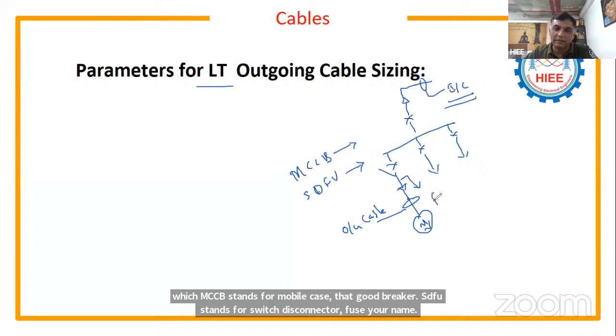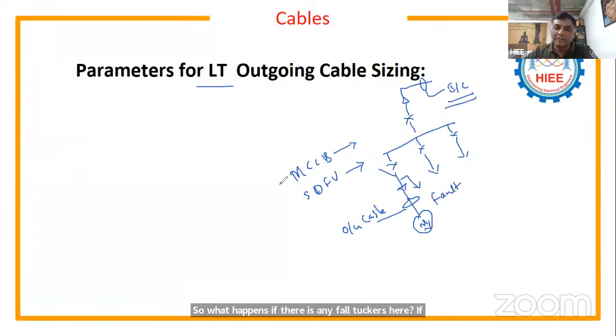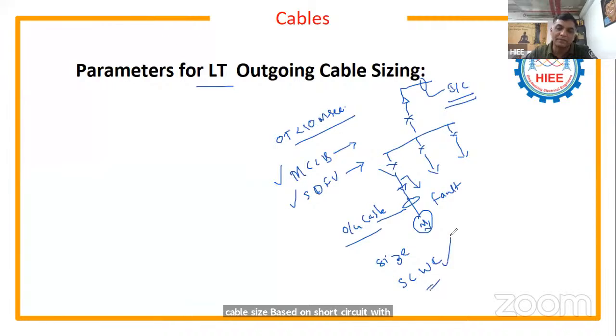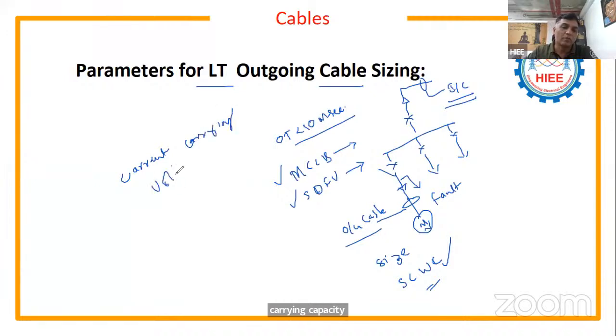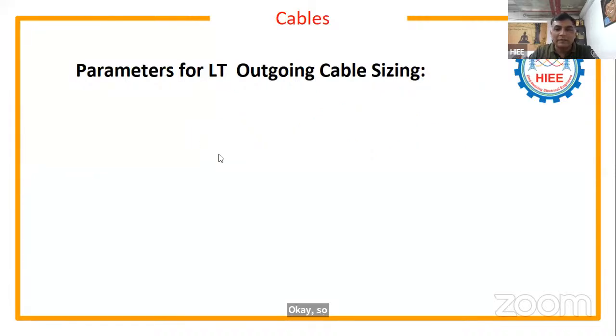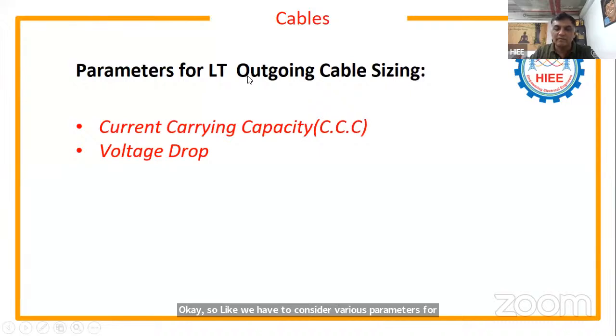So what happens if there is any fault here? If there is any fault here, this MCCB or SDFU operates instantaneously, meaning the operating time of the breaker or switch is less than 10 milliseconds. So for this reason, whatever the outgoing cables, we don't consider the cable size based on short circuit withstand capacity. Outgoing cables are decided based on current carrying capacity and voltage drop. Okay, so we have to consider various parameters for LT outgoing cables. The cable size is decided based on the current carrying capacity and voltage drop.